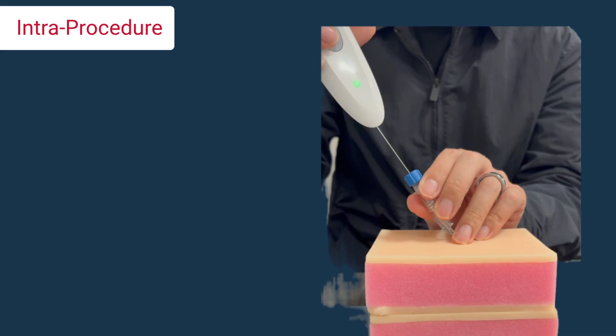Now we cauterize. Hold the cautery button for a minimum of 10 seconds to heat the device to nominal temperature, which corresponds to 18 green flashes. Continue to cauterize the biopsy site for a minimum of 10 additional seconds for a standard case or up to 30 additional seconds per operator discretion.